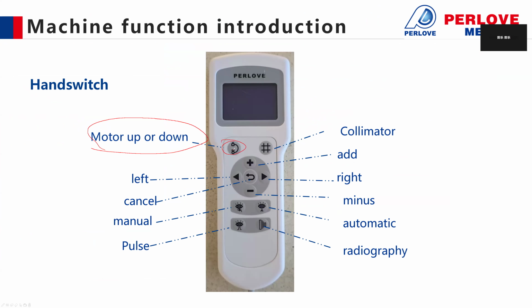Press this button and press the add and minus to move up and down. The second is for the collimator window; we can change the collimator window size. And this button is to choose different exposure modes. This is the function of the hand switch. It's very simple. It helps the doctor to change the machine, but the hand switch doesn't have the exposure function. It can only change movement, collimator window size, and exposure mode.